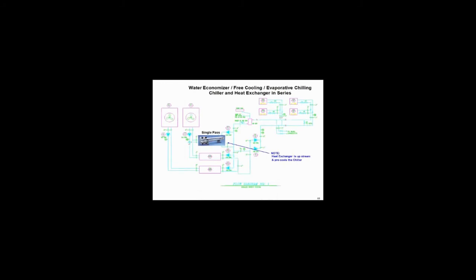Kind of last but not least as we go through this, I want to go back to what we're seeing in the marketplace with this integration. And what we're seeing is a dedicated cell to the water-side economizer. We're seeing heat exchangers in the position of being in series with the chiller plant to where we can precool the 58 degree water going to the chiller plant to 55, 54, take some load off the chiller plant. And we're seeing a dedicated cell of cold water to the water-side economizer, two pipes out to our towers and back. Another set of cells to the traditional chillers so they can run at the same time. You can do it any way you want to, but this is what we're seeing. This is kind of probably going to become the design. The message is this way you can maintain your head pressure control, you can keep the temperatures elevated on the chillers that are running, and you can have as cold water as you need for your water-side economizers. So the message real simple is pay attention to this. If you don't want to do this, okay, but you've got to find a way to handle the head pressure control.